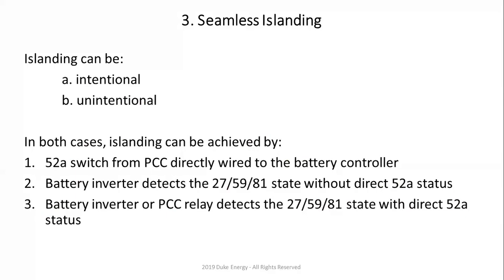Then number two, our second option, was we let the battery inverter detect the islanding based on the 27, 59, and 81 settings, where 27 is under voltage, 59 is over voltage, and 81 is under frequency or over frequency, right? Without the direct 52A status. The reason we wanted to do that is because if you ever build a microgrid, you might not have everything aggregated within your system. So essentially, we wanted to see, is that doable, right?